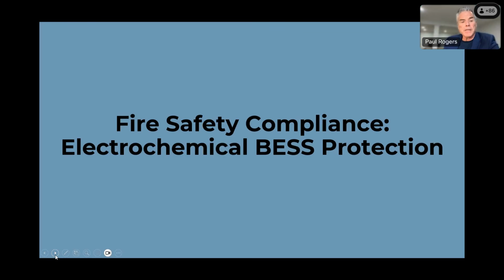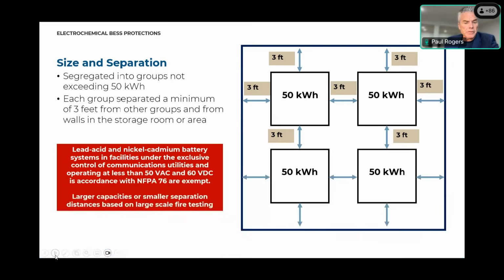Fire safety and compliance, from the electrochemical side and the BESS. If these things are going in, size and separation matter. The maximum allowable quantity you can have inside a room is 50 kilowatt hours, and we call these groups. As you can see in the diagram, we have 4 groups, each needing to be 3 feet away, even from the walls themselves.